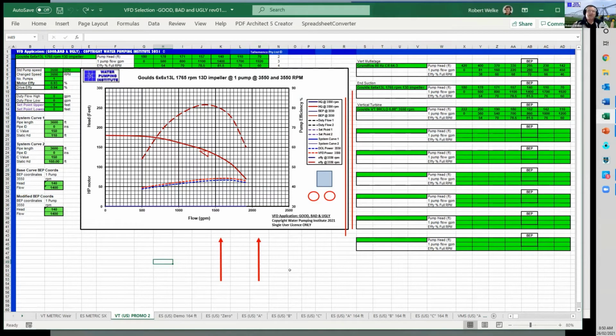It represents a pump curve, pretty much as you see it. It's got a pump efficiency curve, a head quantity curve, and power curves. This particular curve has been set up to run both direct online and VFD. You can see the two curves at the bottom here, horsepower related to the axis on the left. The blue line is the direct online horsepower, and the red curve is the horsepower with a VFD fitted.